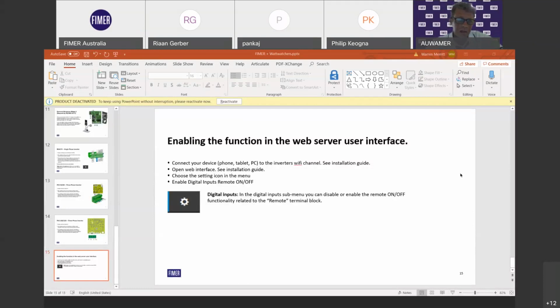Here you see a single line diagram of a single phase installation. You'll see the Wattwatchers module in the middle and the inverter on the far right-hand side. It's a pretty simple diagram — all we're doing is using one of the load switchboard load relays from the Wattwatchers to activate a contactor, which sends a voltage-free signal across the DRM0 remote on-off. So all we're really doing is shorting the two contacts.